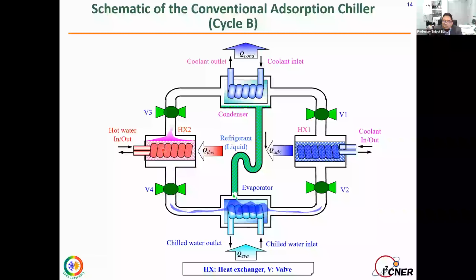What we are doing here is we close all 4 valves, and instead of cooling water, we use some hot water here. So we are preheating this bed, and at the same time, instead of hot water, we are using cooling water here, and pre-cooling this one. This bed will go into desorption mode in the next 7 minutes, and this one will work in adsorption mode. That's why we call it the preheating and pre-cooling mode of this cycle.